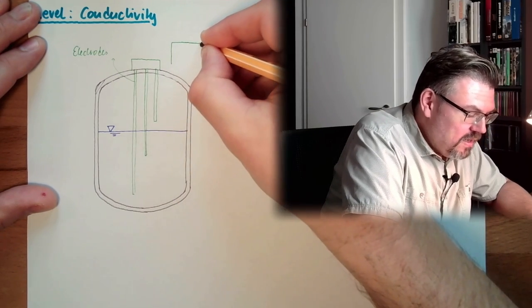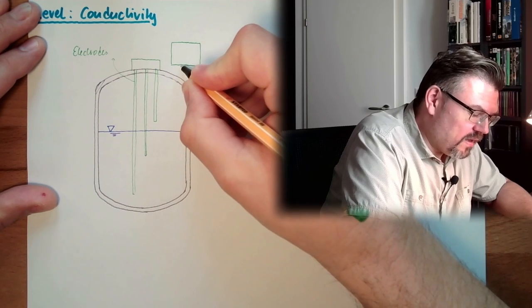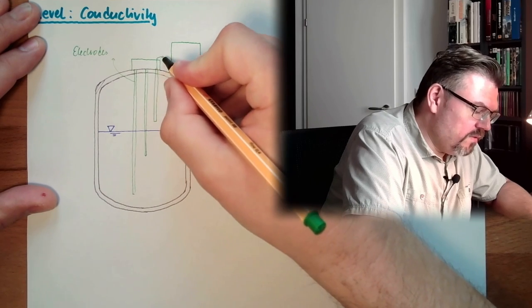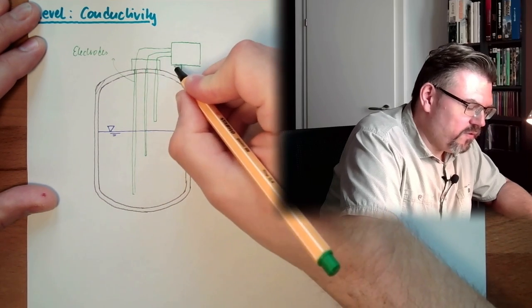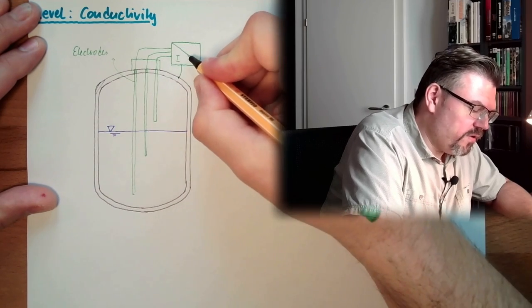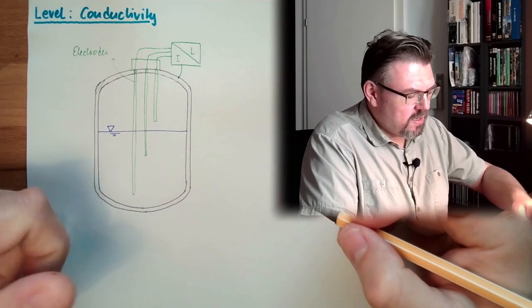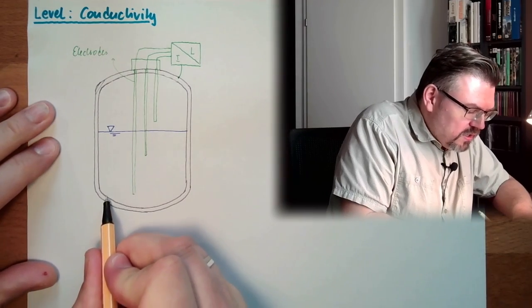And there would be even the possibility, if the wall of the tank is also conductive, then you could even use this. And this, for instance, would look like, so here we measure the current. If current is running, then we have the level. This for instance would check this level, this level, this level. This would be the switching levels.